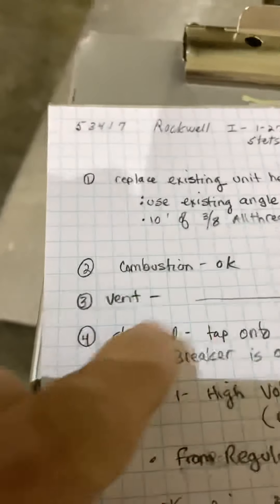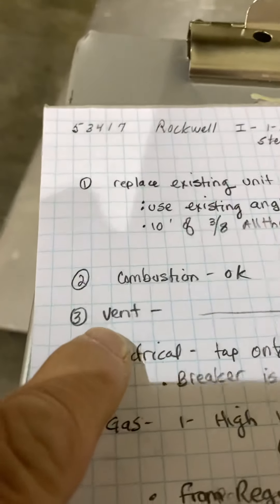Combustion air is obviously okay in the big open warehouse. The vent, our new unit will vent out in five inch draft hood. I'll give you a five inch draft hood, a couple one footers, a six inch, and an adjustable so you can get pretty much anywhere you need to.